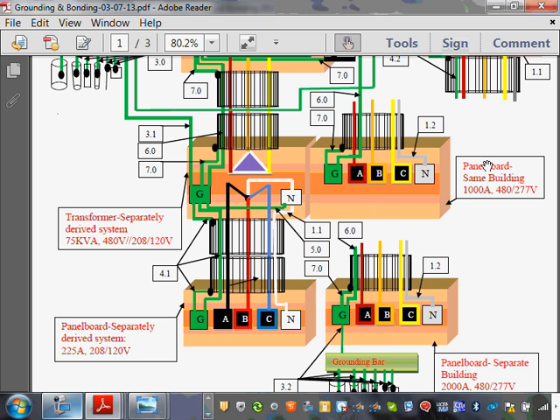So I wanted one grounding point, so I had them take it all the way back to the building entrance grounding bar. Anyway, it worked fine. Did you also pull another? Yeah, there's two grounds. So in addition to this, you pulled another ground all the way back to the service. I don't see if that stabilizes your low voltage system.